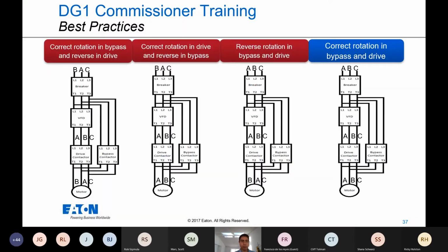So let's move forward here. Once you have programmed the correct parameters, be able to bump your motor. The right rotation is critical because you can have scenarios where the drive is running correctly, but not the bypass, or inversely the bypass and not the drive. They could be both running in reverse, but to achieve the correct rotation, make sure your input lines are wired appropriately, output from the VFD to the contactor and from the contactor to the motor.